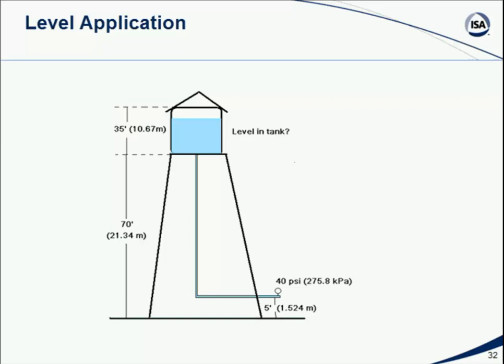Well, we've got a variety of numbers here. We know that the tank itself, at the bottom of the tank, is 70 feet above ground. We also know that our measurement device here is 5 feet above ground. So when there's nothing at all in the tank, when the tank is empty, presuming that we don't suck the water out of the pipe that goes up to the tank, we know that we will have a 70 minus 5, or a 65-foot high column of water when the tank is absolutely empty. When the tank is full, we know that we'll have 35 feet more than that. So we'll go all the way up to what is it? It's 70 plus 35. You do the math.